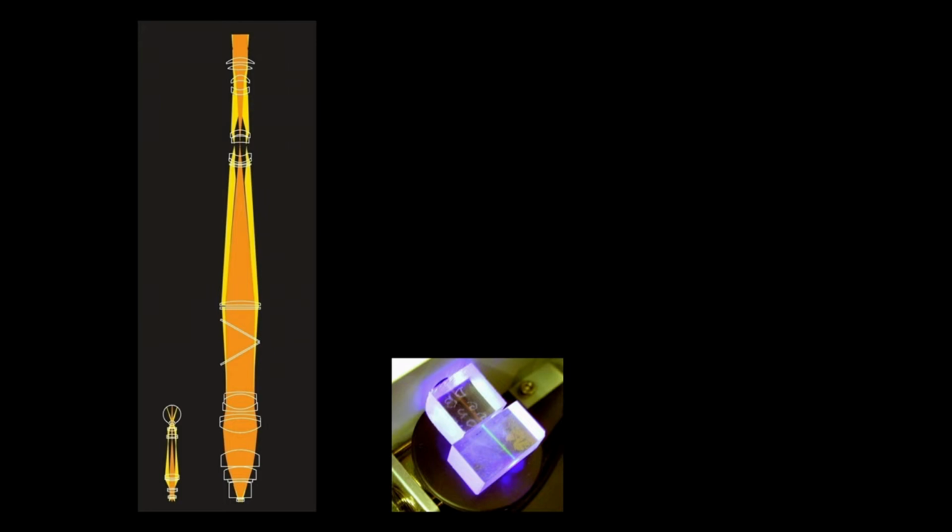Each one of these individual lens elements can be up to 80 millimeters in diameter. And you'll see that there are very many of them, and some rather interesting looking elements such as these off-axis compensator plates and dichroics, which are inside the objective lens, which allows us to perform wide-field epifluorescence imaging. There are no nonlinear elements in the Mesolens. We use simply ray optics and a combination of nous, or knowledge, and Zemax to design the lens prescription.